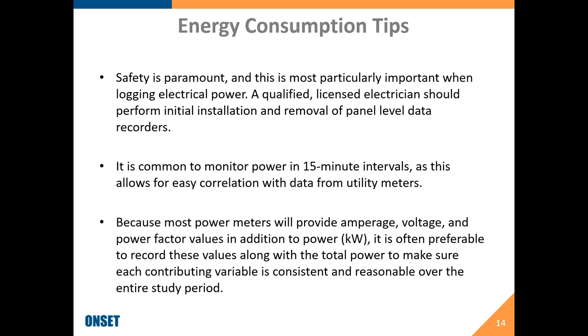Since most meters will provide a variety of different power quality factors like amperage, voltage, and power factor, in addition to your kilowatt hours, it's always best to keep an eye on these when you're reviewing the data post-deployment, specifically when one of these variables drops out or if there's any inconsistency. It can point towards some other issues in the system that you're studying.